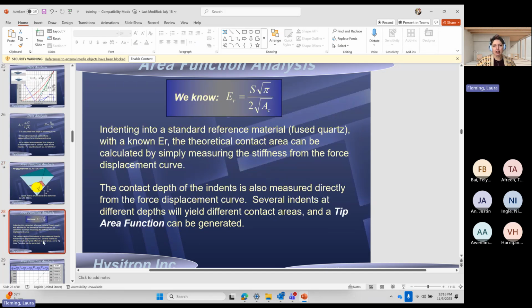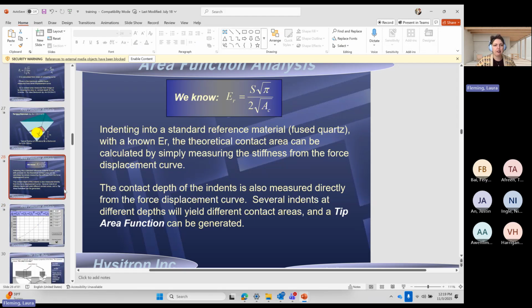How can we fix that? So what we say instead is, wait, I have a sample that has a really well-known, well-defined reduced modulus of 69.6 that is constant as a function of depth. It doesn't have surface irregularities. It's well-known, well-defined, well-proven, and that's fused quartz. So what we do is we indent into the fused quartz and we switch this equation all around. We say, okay, the stiffness, I'm getting that from the graph, that information I have. I know what this reduced modulus should be, 69.6. So let's go ahead and solve for the contact area at this depth. And if you do it over and over and over again, you can start to define that tip area function. So this is all handled through the software, but we should understand where this is coming from.